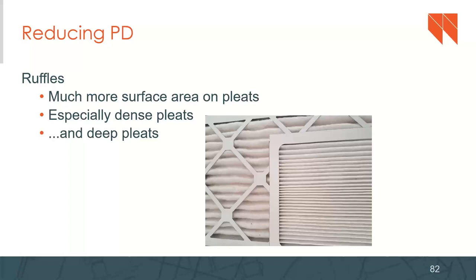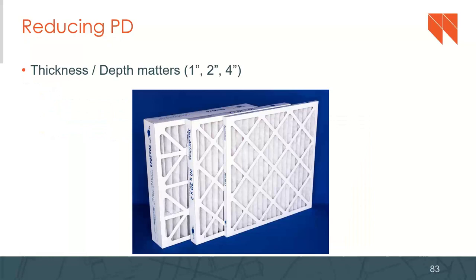What are some ways to reduce pressure drop in general? The pleats, the ruffles, there's much more surface area on pleats, especially the dense, deep pleats. And so looking at these thicker, bigger filters, right? The thickness does matter. And so 1 inch, 2 inch, and 4 inch is shown here.